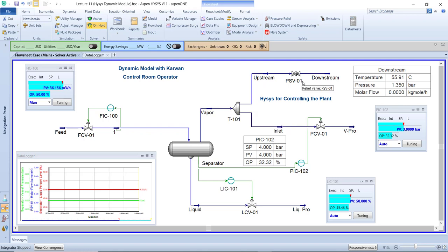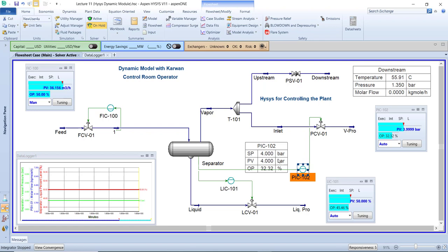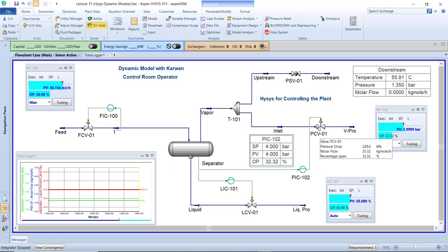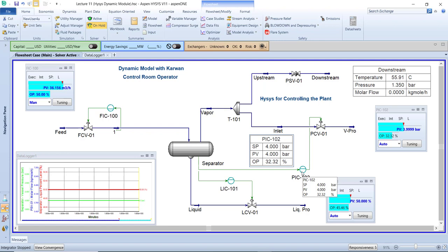We have two lines: the normal operation PCV pressure control valve, and the PSV safety line. This control valve PCV is controlled by a special controller — exactly as in real life in all oil and gas industry. The control valve is located in the field and the PIC (pressure indicator controller) is located in the control room. All the control logic is inside the controller.